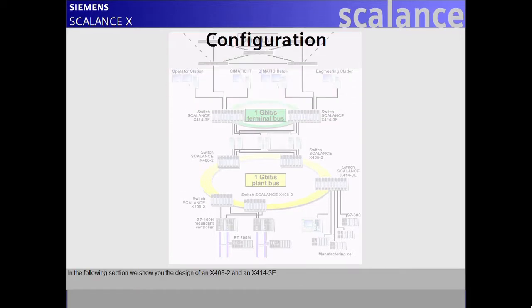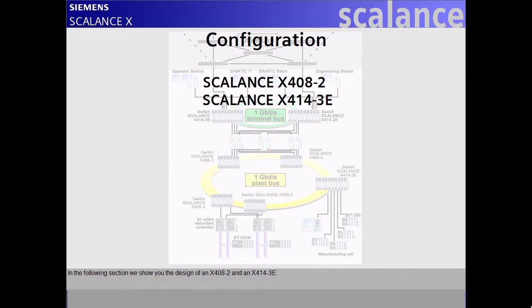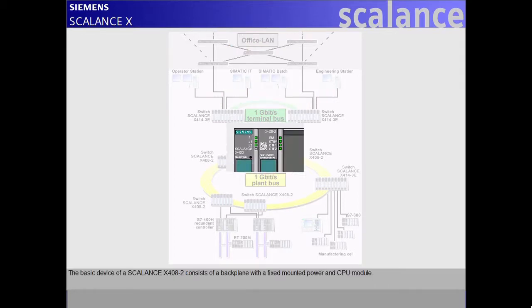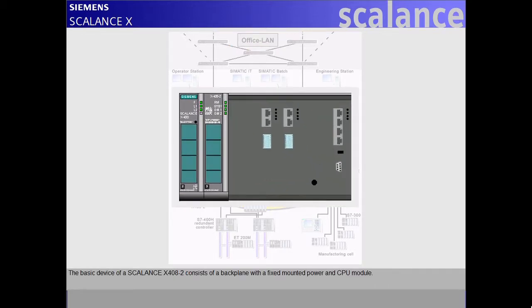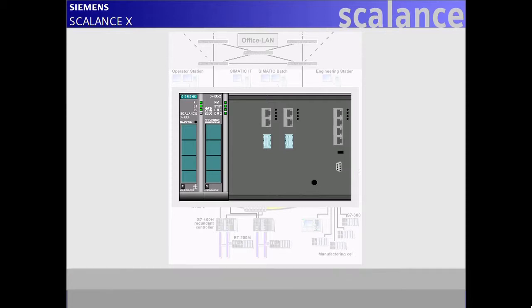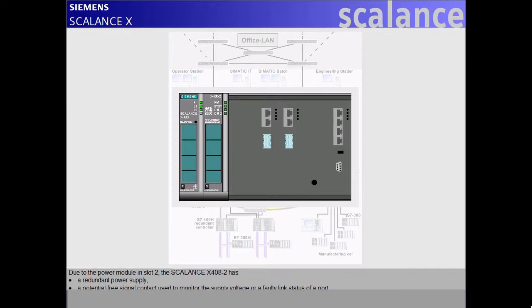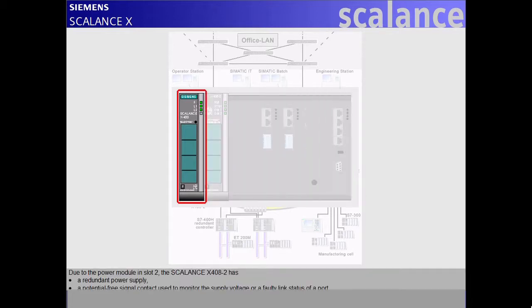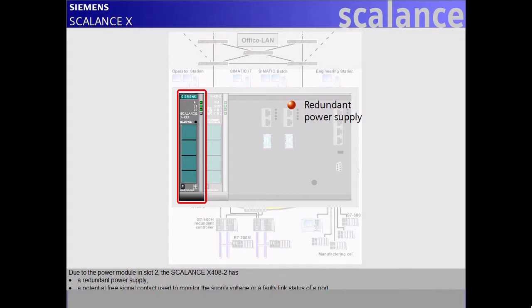In the following section, we show you the design of an X408-2 and an X414-3E. The basic device of a Scalance X408-2 consists of a back plane with a fixed-mounted power and CPU module. Due to the power module in slot 2, the Scalance X408-2 has a redundant power supply.